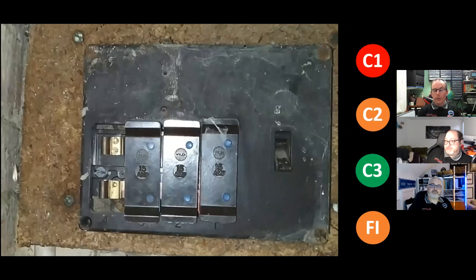That along the bottom edge there, that's a slide, going to be live, isn't it? And the other thing that's wrong here is if you look at those three fuses, they're not actually in line. The reason they're not in line is because the plastic shields are missing from all four of these positions. So if you take another fuse out, you're going to get the same situation again. Yeah, what a mess.